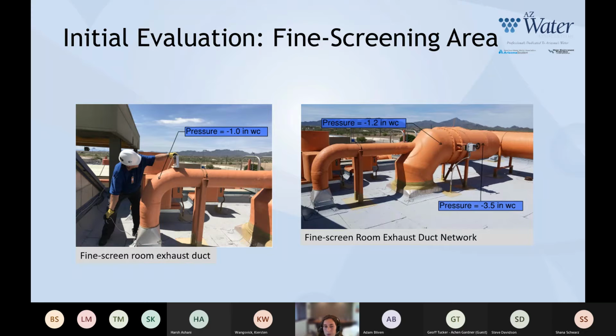We then went up to the roof, and you can see where the foul air ducts all connect. You can see my colleague Steve here measuring the duct static pressure. So this skinny duct where he's taking the measurement from, that was actually the channel header. So it was pulling foul air from the fine screen influent channels, and then it was connecting to this larger, this is the fine screen room foul air duct.